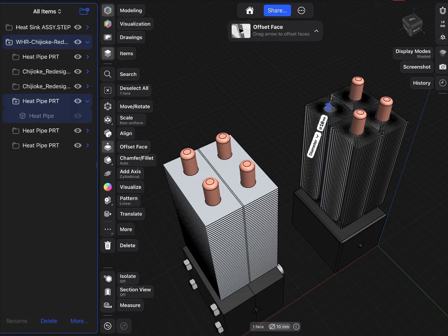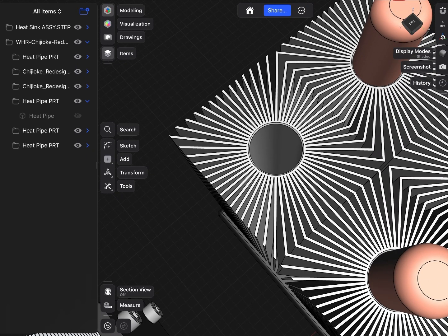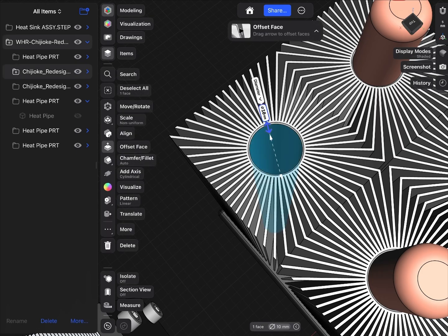There's also some bonding material there, a thin layer of thermal epoxy, that glues the copper tubes to the fins to allow for a contact continuum, which allows for easy heat transfer and conductance of heat, and allows the heat to be rejected via these fins.